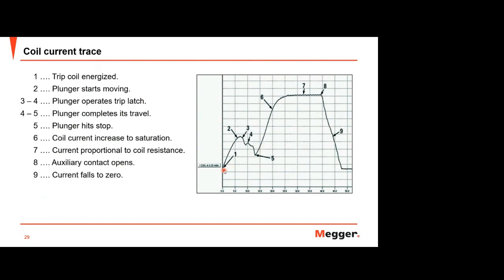As you can see, when a trip coil is first energized, current flows from zero. The current flows through its winding, and the magnetic lines of force in the coil will magnetize the iron core of the armature, or plunger, in the middle part of the coil, inducing a force in the armature. The current flowing to the trip coil increases to the point where the force exerted on the armature is sufficient to overcome the combined gravitational and friction forces which may be exerted, pulling the armature through the trip coil core. So the magnitude of the initial current, from this point to this point, is proportional to the energy required to move the armature from its initial rest position. It will depend on that.